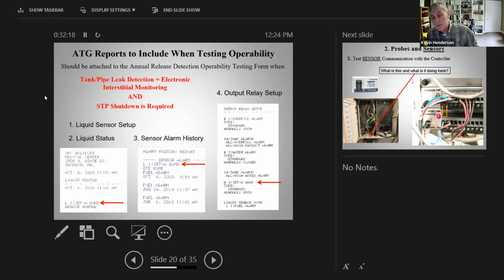And you can connect that to like 8 of them in Veeder. So you do have these external relays in the system. They are set up. You see this one is connected to the Jet A sump. And so that's the way that you can verify that it is at least set up to shut down the STP.